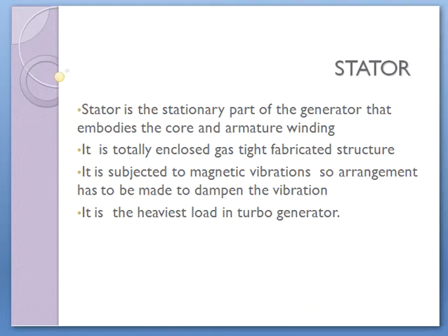Stator is the stationary part of the generator that embodies the core and the armature winding. It is a totally enclosed, gas tight, fabricated structure. It is subjected to magnetic vibrations, so arrangements have to be made to dampen the vibrations. Since it holds a lot of conductors for generating a large voltage and a very high current, it is the heaviest load in the turbo generator.